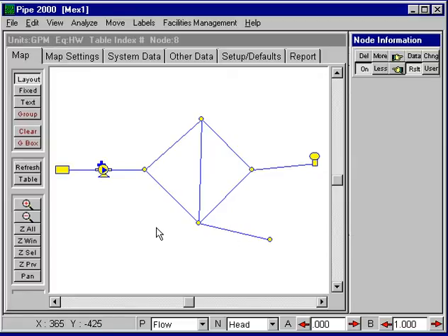I want to continue illustrating EPS setups with this example that, in the last video, we set up a 24-hour simulation with a one-hour increment. We provided tank data. This had a starting level of 200, a max level of 220, and a minimum level of 180. What we want to illustrate now are the two other types of data, the demand pattern data and the control switch data.